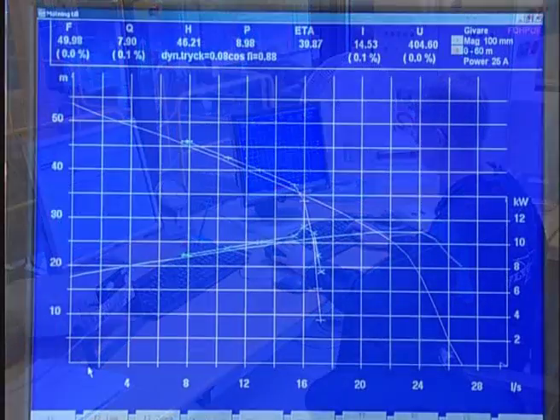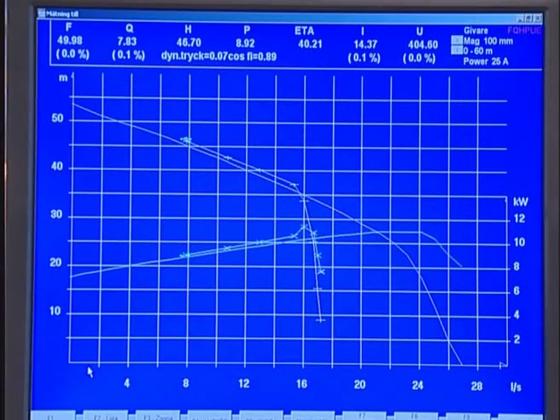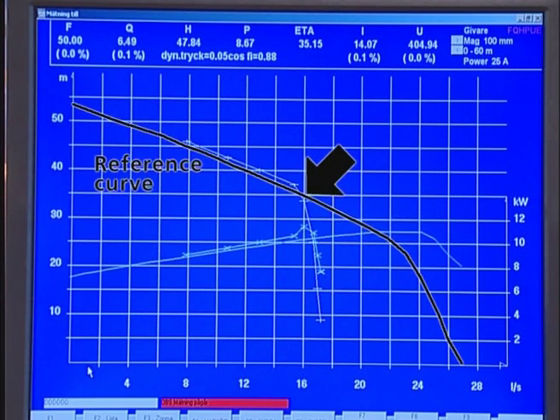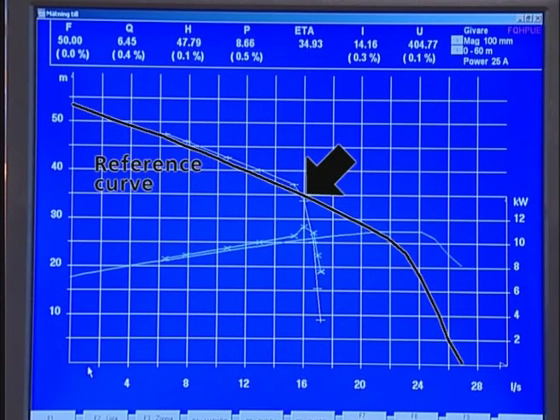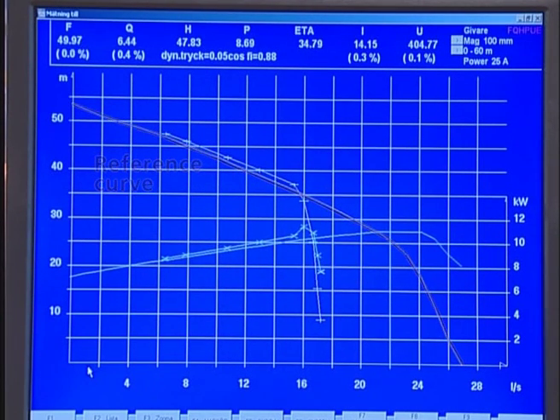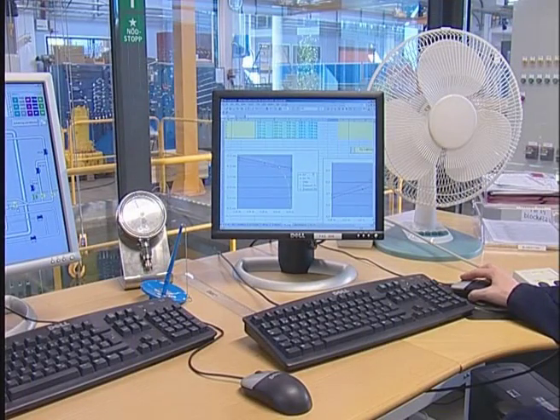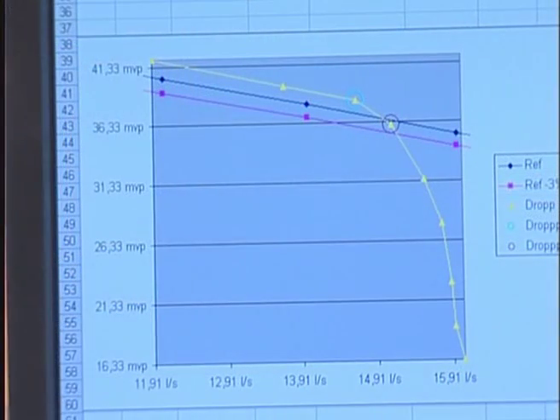A number of duty points are measured in each test run. The duty points are constantly being compared to a pump performance reference curve. We can see a number of measured duty points in a typical drop curve. Notice how the pump performance at a certain point drops, deviating from the reference curve. At this point, we have cavitation affecting the pump performance, and we know that the measured inlet pressure at that flow is what the pump requires for proper performance. The measured test curves are processed by the computer. The same routine is repeated for different positions of the inlet valve until we have a complete NPSH curve.